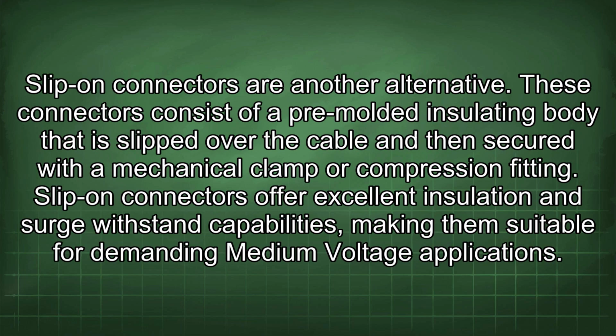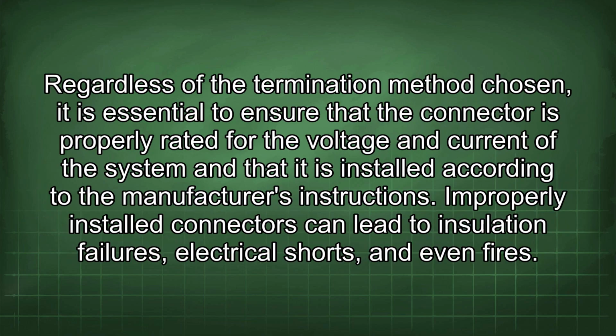Slip-on connectors are another alternative. These connectors consist of a pre-molded insulating body that is slipped over the cable and then secured with a mechanical clamp or compression fitting. Slip-on connectors offer excellent insulation and surge withstand capabilities, making them suitable for demanding medium voltage applications. Regardless of the termination method chosen, it is essential to ensure that the connector is properly rated for voltage and current of the system and that it is installed according to the manufacturer's instructions. Improperly installed connectors can lead to insulation failures, electrical shorts, and even fires.